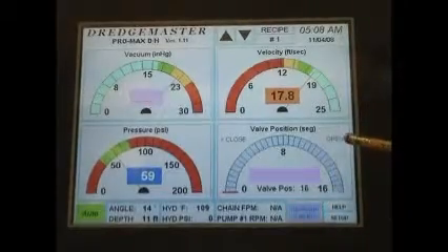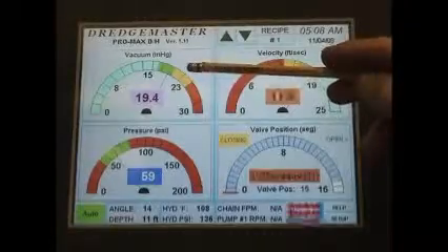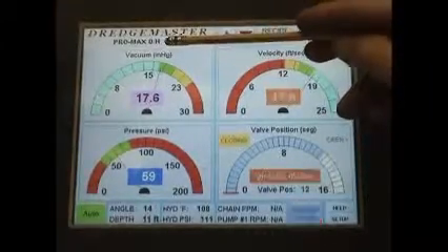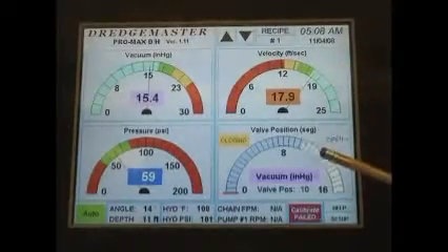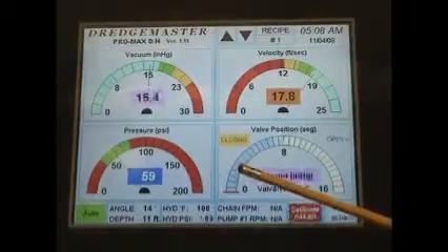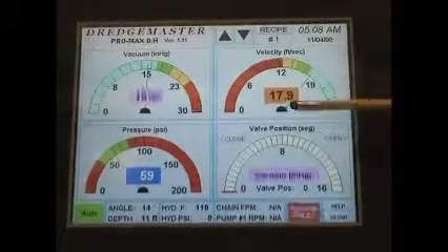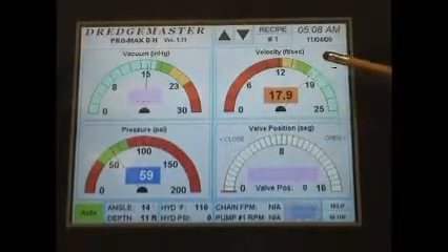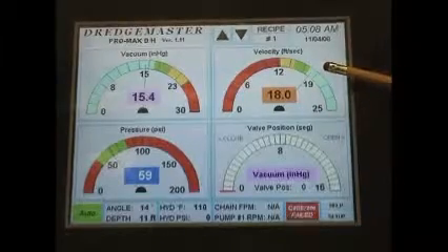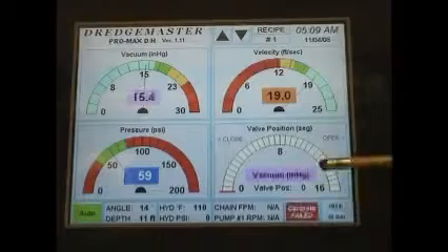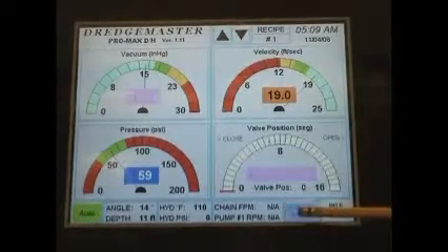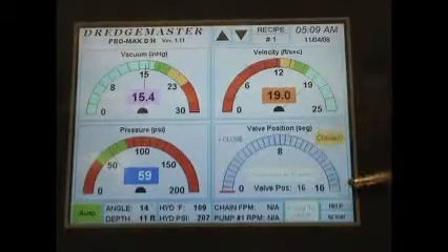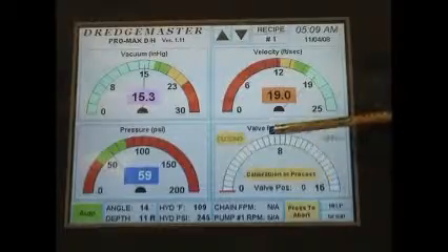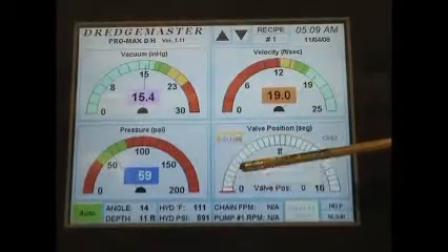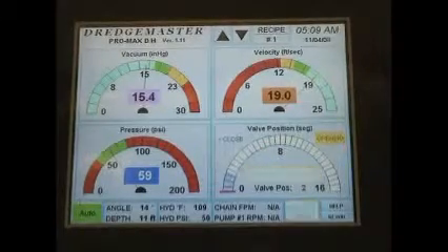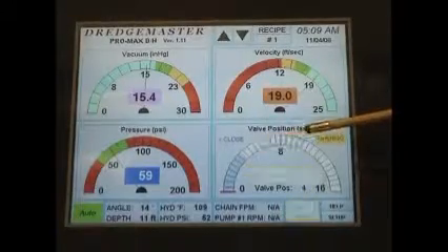What we're going to do is have the operator pull up on the ladder and get the valve back into the turquoise range again in both areas and allow the valve to start closing itself back down. Once the valve has fully closed and both of these must remain in the turquoise range, in other words the operator has lightened up his load, he's going to press the calibration fail button to activate the calibration process. The valve immediately opened itself all the way open, and now the valve has fully closed itself, and the valve is continually going through the calibration as far as stepping itself open. It's going to keep opening up all the way.